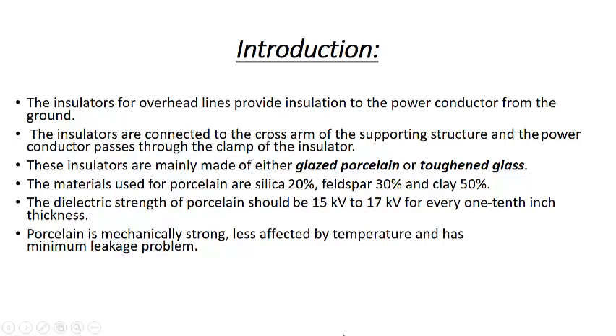The insulators are usually made of glazed porcelain or toughened glass. This porcelain contains 20% silica, 30% feldspar, and 50% clay. The dielectric strength of the porcelain is usually from 15 kV to 17 kV for every 1/10th, that means 0.1 inch of the thickness. Also, porcelain is mechanically strong, less affected by temperature, and has minimum leakage problem.